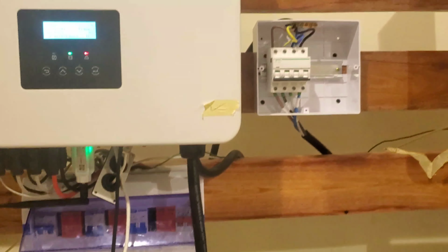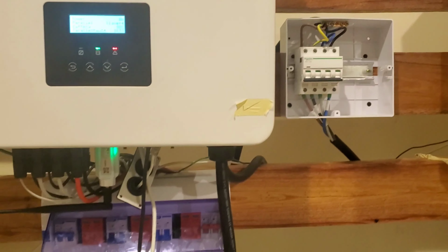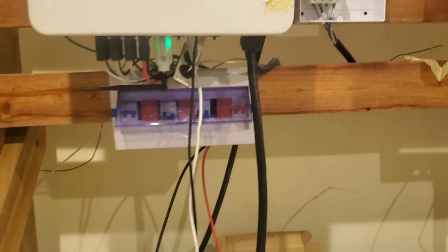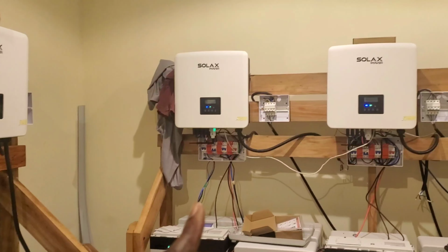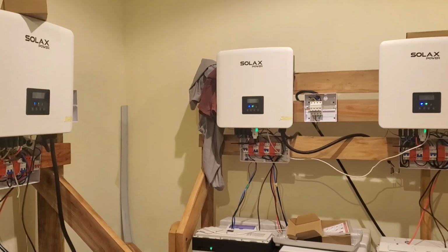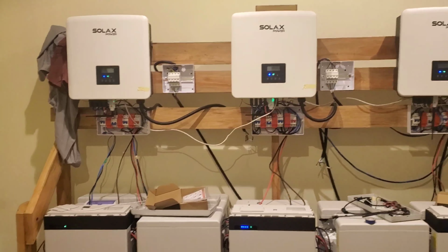Now it's showing parallel fault error, but once we turn everything back on, let me see if I can show you. Showing parallel fault error. But once we connect everything, guess what? It is no longer a slave. It just becomes an independent. So what we're proposing to do is remove this one, put it where number 6 is, and then we'll run 5 inverters for our test. So 5 times 15 is 75 kilowatts.